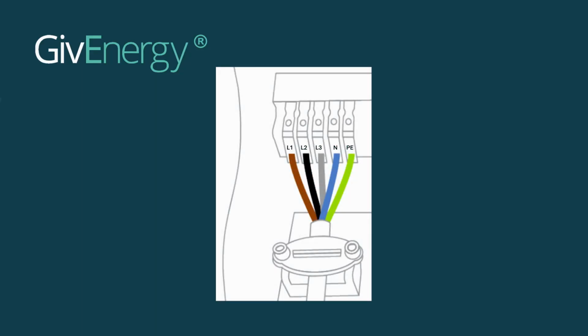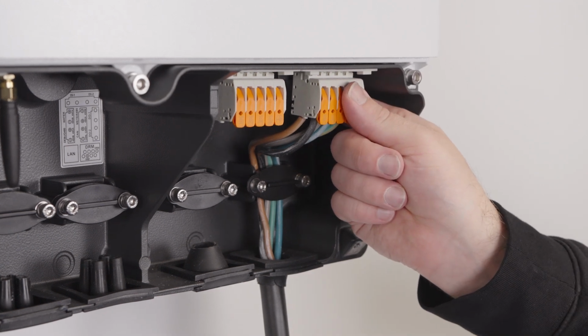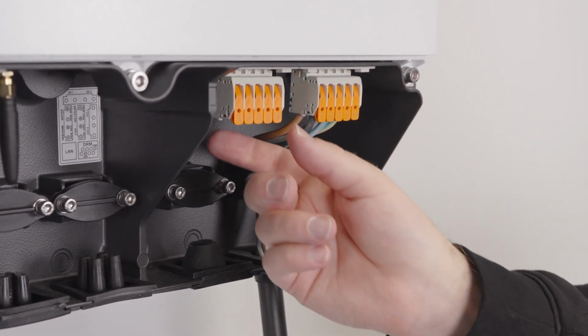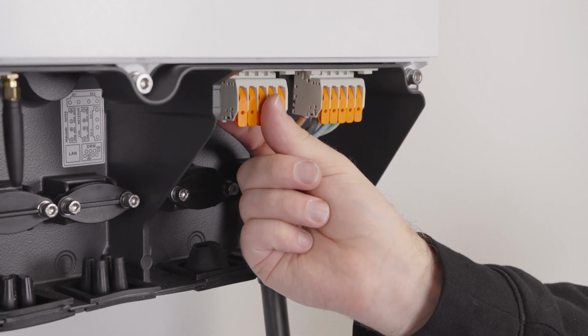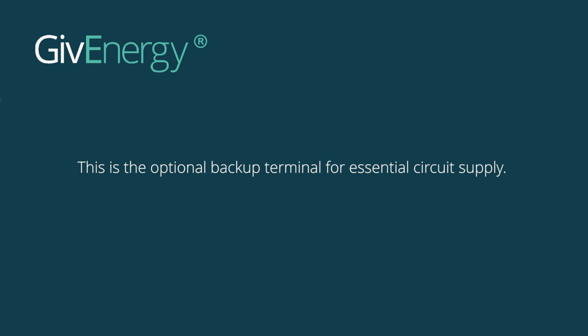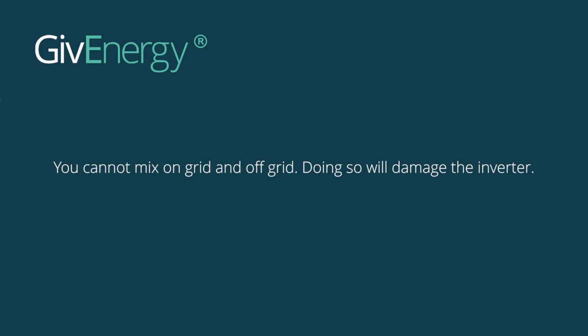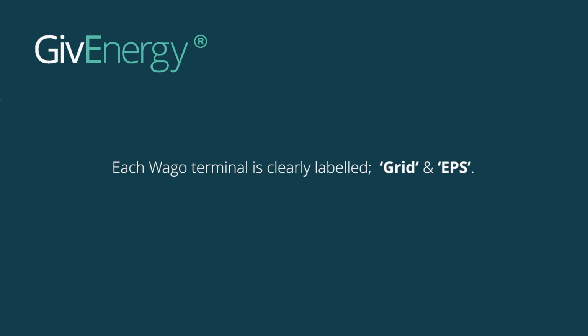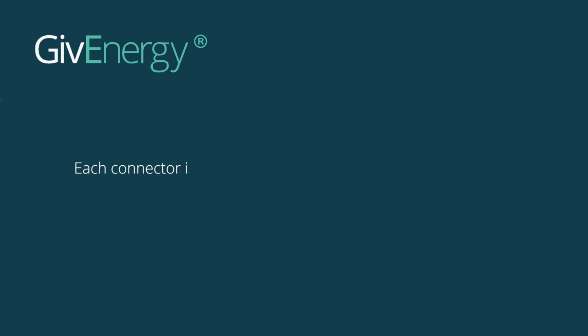Next, we need to ensure that phase rotation is correct on each of the grid terminals. The terminal on the far right here is for grid connection. The next one along is our emergency power supply or EPS. This is the optional backup terminal for essential circuit supply. The terminal isn't for whole home backup. You cannot mix on-grid and off-grid. Doing so will damage the inverter. Each Wago terminal is clearly labelled grid and EPS. Each connector is also labelled L1, L2, L3, neutral and earth.